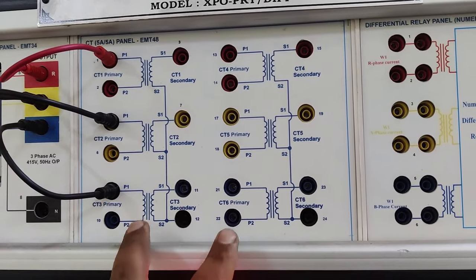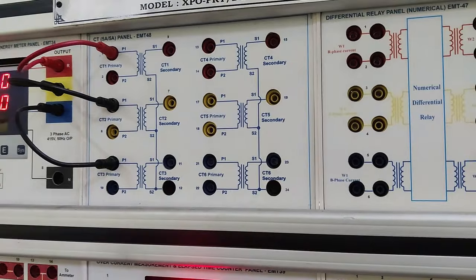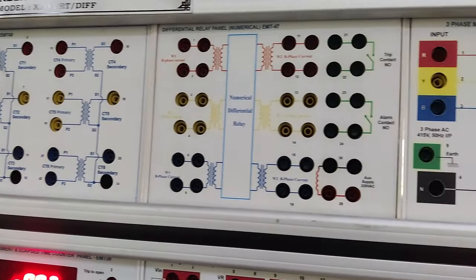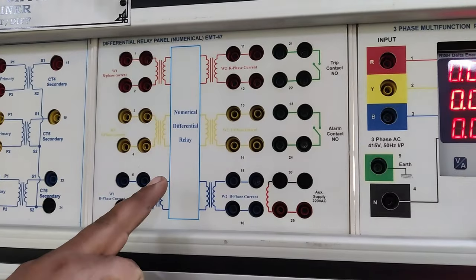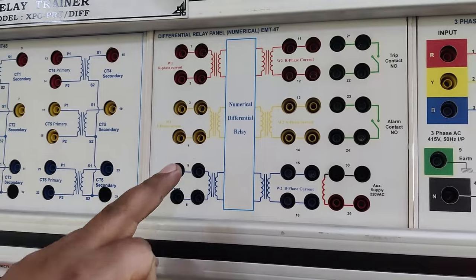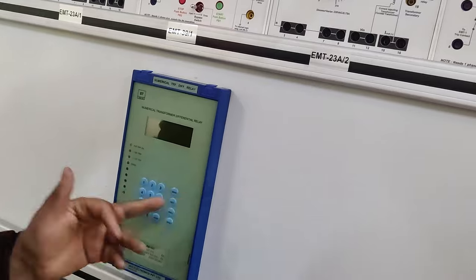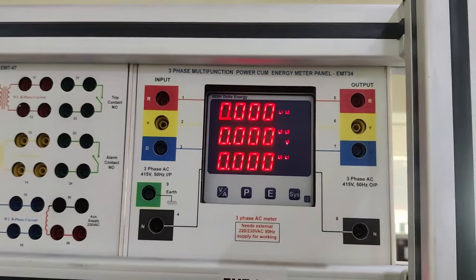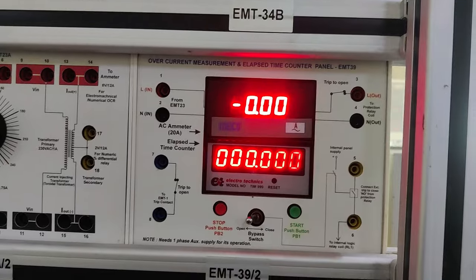After that we have the CT panel — actually we have three CTs. We can connect the CTs in star or delta depending upon the requirement, accordingly as the transformer in which they are connected. We have a numerical differential relay panel. These are the three-phase numerical differential relay contacts, and from this microprocessor-based numerical transformer relay you can change the settings, which I will be showing during the practical. This is also another three-phase multi-functional energy meter.